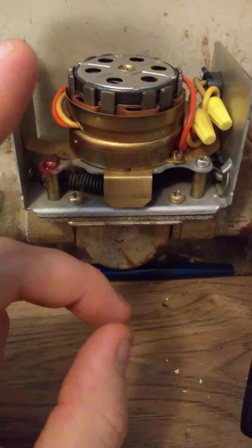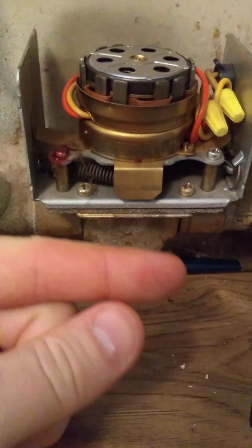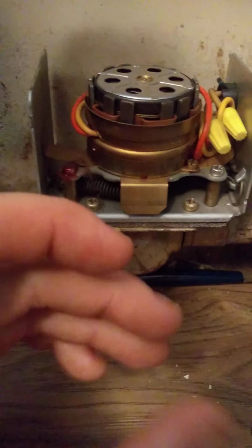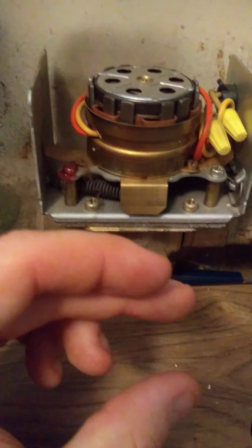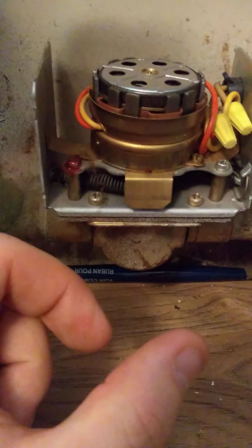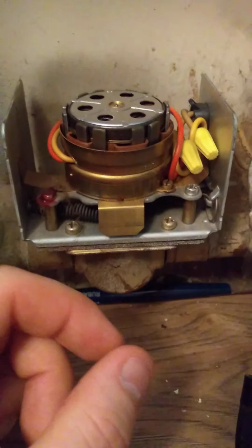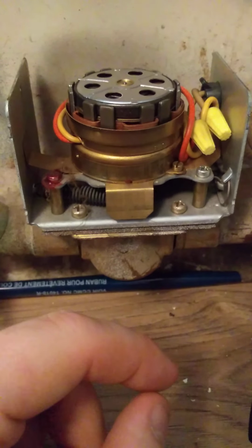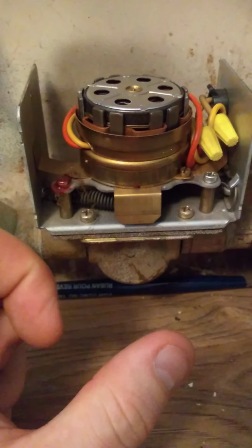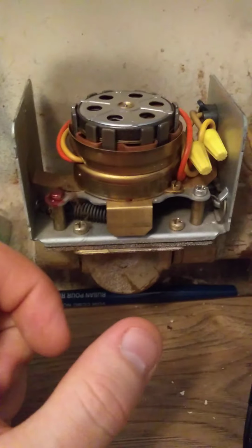I could take all this stuff off and just put a little knob on there. And when I want heat, open it up. When I don't want heat, close it up. If I want a little bit of heat, just open it a little. If I want a lot more heat, open it more, and that'll increase or decrease the flow. And I have lived in places that had such a system where the loop circulated, and then each heat register was basically its own zone, and you would just open or close the flow of hot water manually.